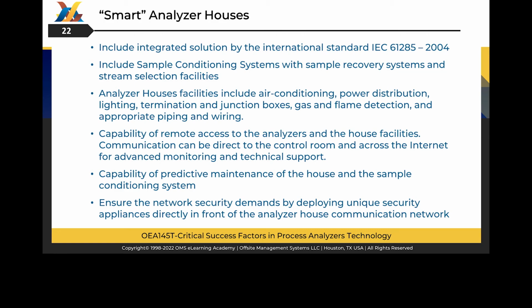So-called smart analyzer houses is an effective solution for integrated solutions per the international standard IEC 61285-2004. This house typically includes sample conditioning systems with sample recovery and stream selection facilities, air conditioning, power distribution, lighting, termination and junction boxes, gas and flame detection, and appropriate piping and wiring.